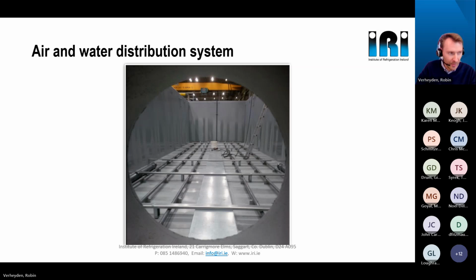Now you see some small PVC pipings below. You see 3 on the left, 3 on the right, completely to the back. These are bubbler pipings. And that's the special thing with external melt, what you don't have with internal melt. Here, we will push some air bubbles into the ice tank. Why do we do this? Actually, this is to have a proper heat exchange between water and ice, just to improve the heat exchange and to force the flow.